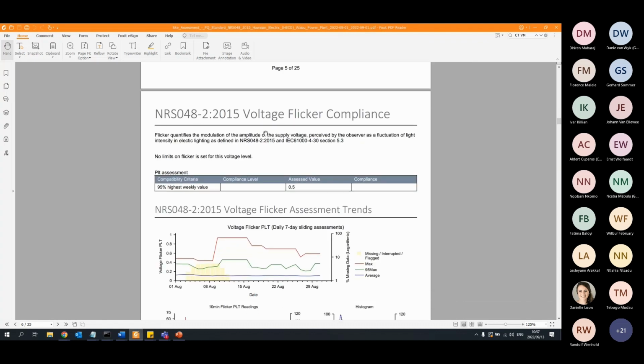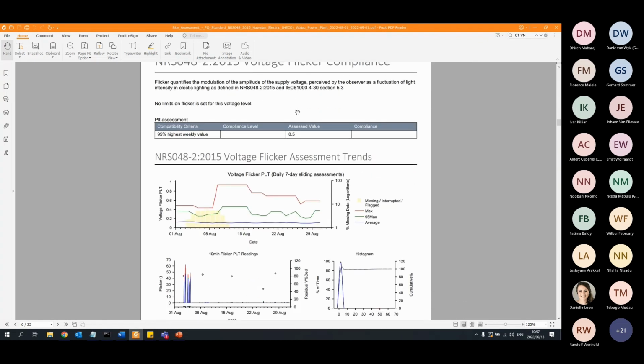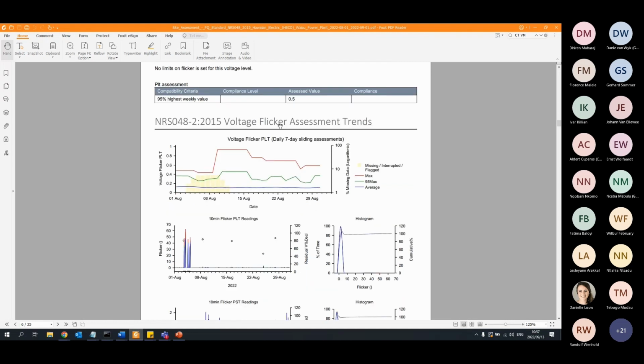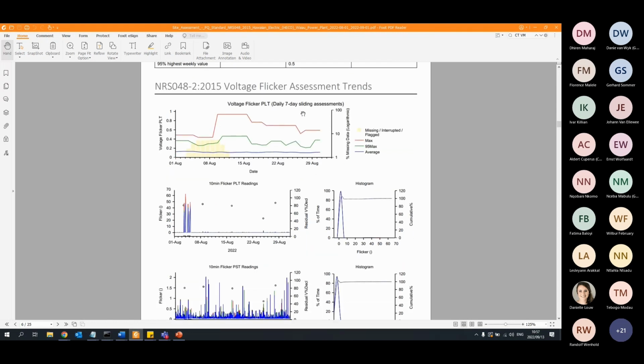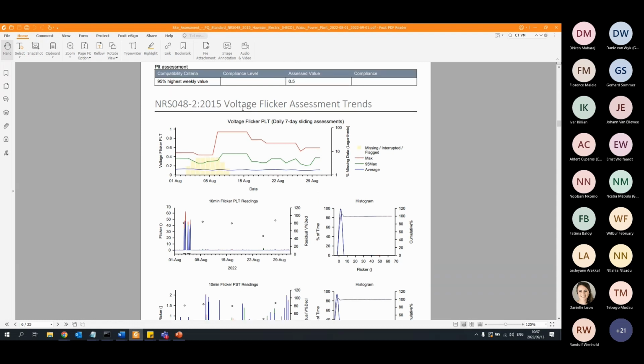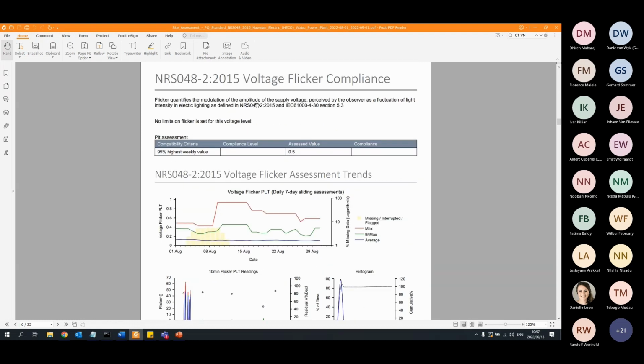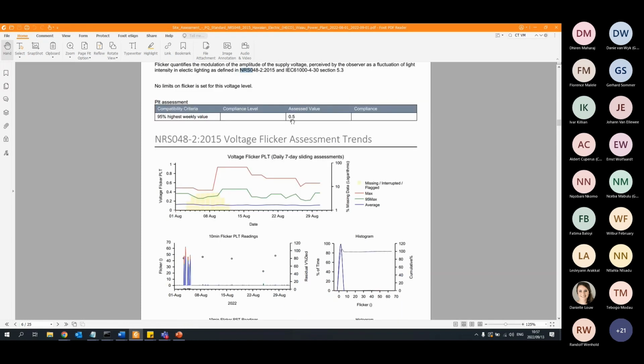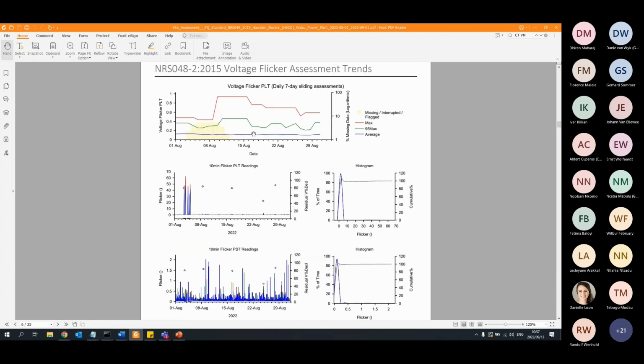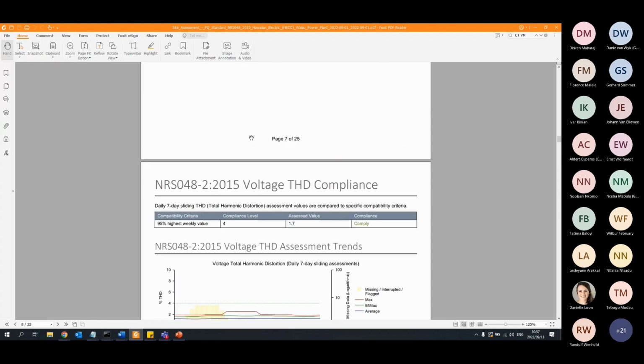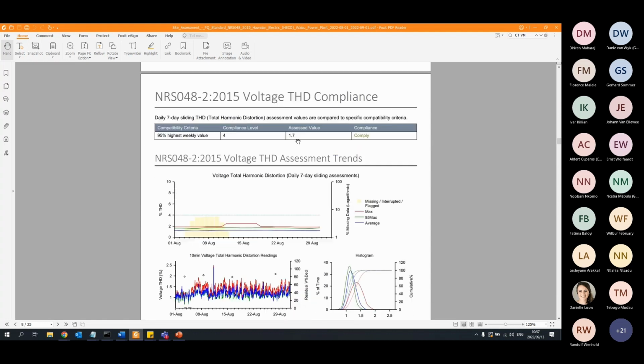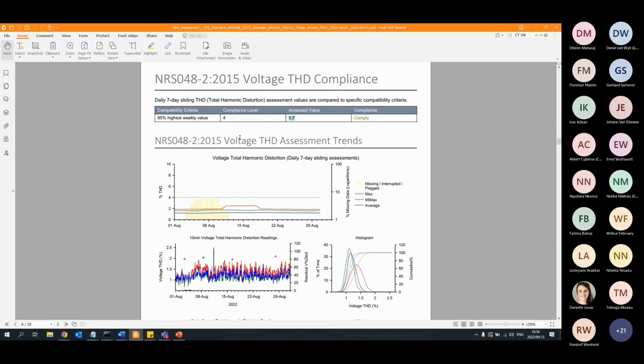Okay, then we have voltage flicker, which is compared to the assessment. For this specific point, because it's 66 kV, there isn't any limit specified in the NRS 048. So the assessed value was 0.5, but there's no compliance level that you can compare it with. And then it's your THD value, which is assessed as 1.7%, which is also well below the 4% level.